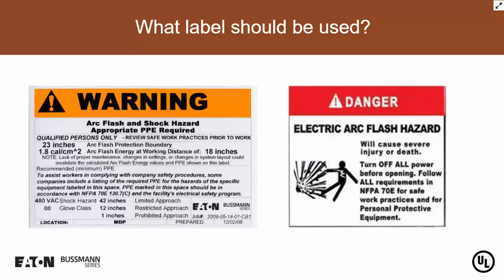Now reverse that. If my SCCR is 50,000 amps, and my available fault current, let's say, is 65,000 amps, now my SCCR is inadequate. And so now I really need to put the right label sticker on my panel until I fix the situation. Because if the electrician goes in there, it could blow up in his face, right? So we are in violation of the National Electrical Code when the SCCR is not adequate for the available fault current. So if the SCCR is adequate, I use the left label. If the SCCR is not adequate, I use the right label until I fix the SCCR and make it adequate for the available fault current.